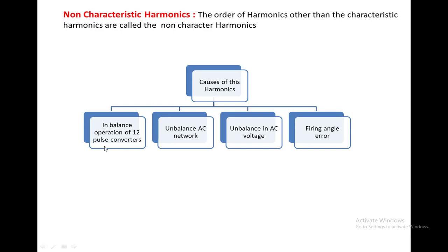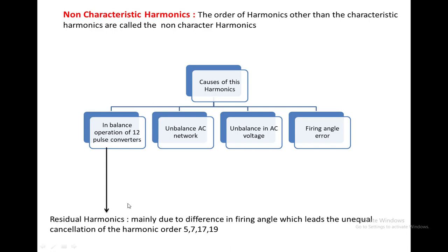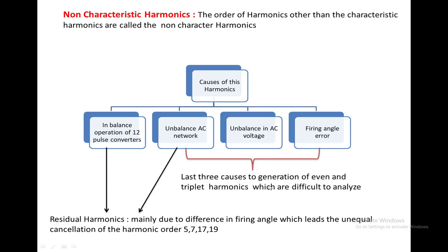Imbalanced operation of a 12-pulse converter means there is a difference in the firing angle of the two converters, which leads to unequal cancellation of harmonics of orders 5, 7, 17, and 19, so these remaining harmonics are nothing but residual harmonics. These residual harmonics are also generated due to imbalance in the network, unbalanced AC voltage, and firing angle error. Because of these three causes, harmonics are generated — specifically even harmonics and triplen harmonics, which are very difficult to analyze.